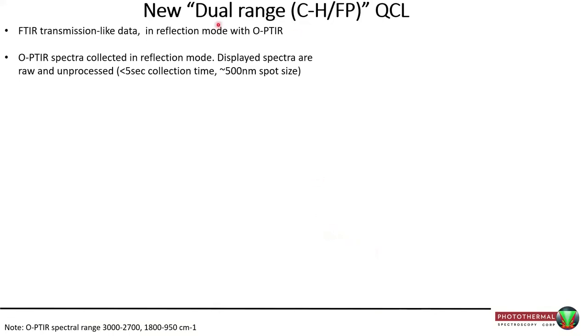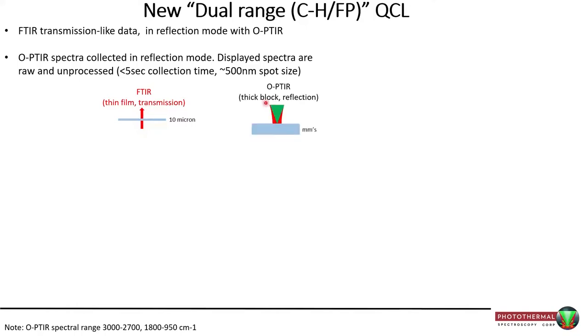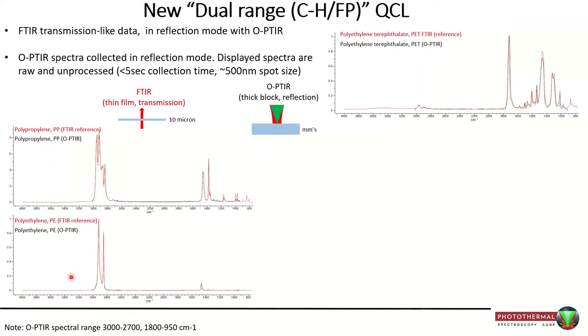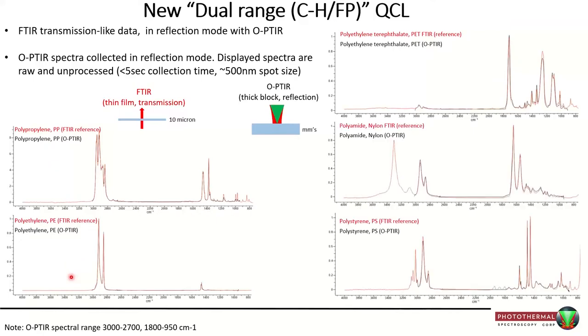To give examples with the dual-range CH fingerprint QCL: all data shown are in reflection mode, giving transmission-like spectra, collected in under five seconds from about a 500 nanometer spot. Comparing FTIR transmission reference spectra on thin samples versus OPTIR reflection on thick blocks — for polypropylene, polyethylene, PET, nylon, and polystyrene — the red FTIR reference and black OPTIR spectra are at first glance almost perfectly overlapped.